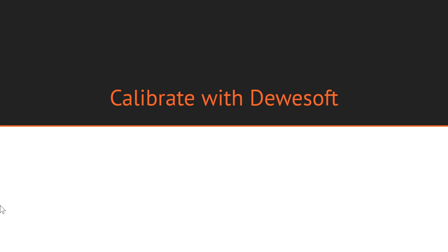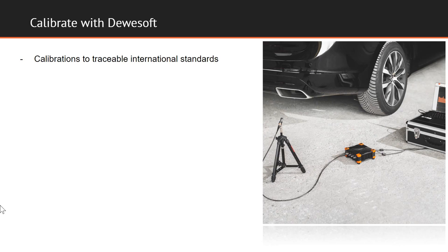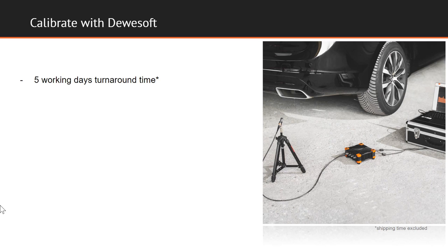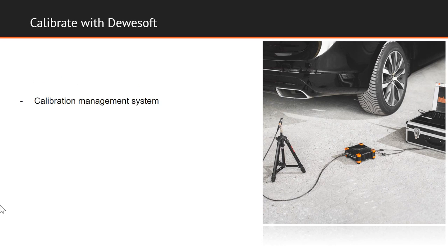In order to achieve this, we paid special attention to our customer needs when shaping our calibration services. To ensure the best possible execution and worldwide standard compliance, we partner up with an experienced, internationally accredited calibration laboratory. As a result of this partnership, we are able to provide a highly competitive service featuring the following: worldwide valid calibration to traceable international standards, meaning the performed calibrations will be valid all around the world. 5 working days turnaround time, and a state-of-the-art calibration management system which is tailored to the user. This way, the user gets notified when calibration is about to expire and the calibration process can be tracked while being carried out.